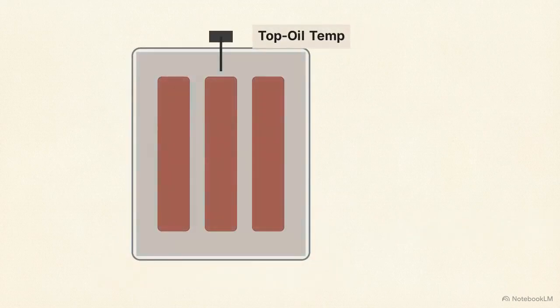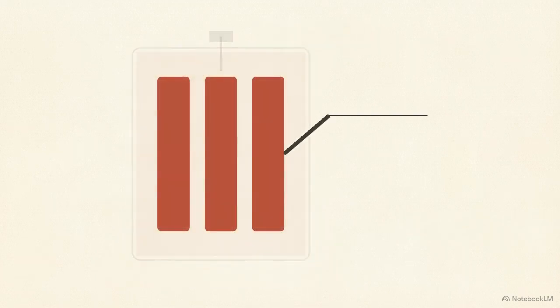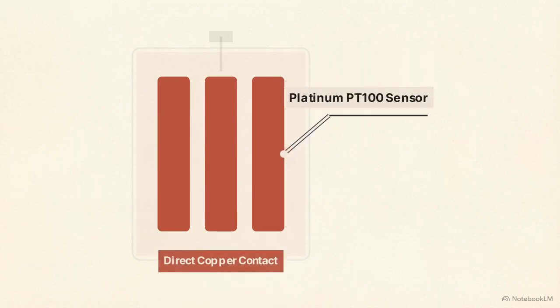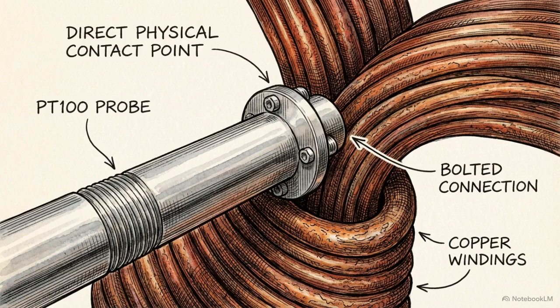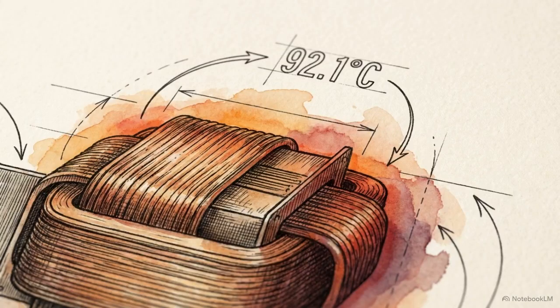This IIoT layer pyramid is the architectural model for predictive maintenance, starting at layer 0, the physical sensor level. Traditional monitoring measures top oil temperature, but oil heats slowly. For an accurate model, engineers embed a platinum PT100 sensor directly against the internal copper coils. By maintaining direct contact with the windings, the PT100 sensor bypasses the oil's thermal delay. It captures instantaneous, second-by-second thermal responses the moment the electrical load shifts.